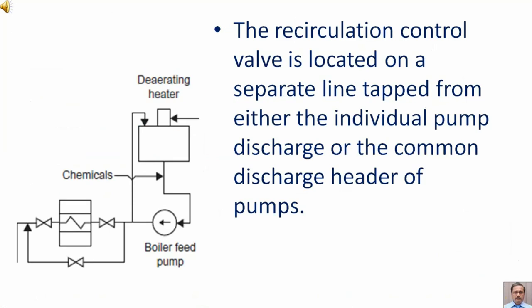In this diagram you can see the boiler feed pump and its discharge header. You can see the recirculation line for this pump. The recirculation control valve is located on a separate line tapped from either the individual pump discharge or the common discharge header of pumps.